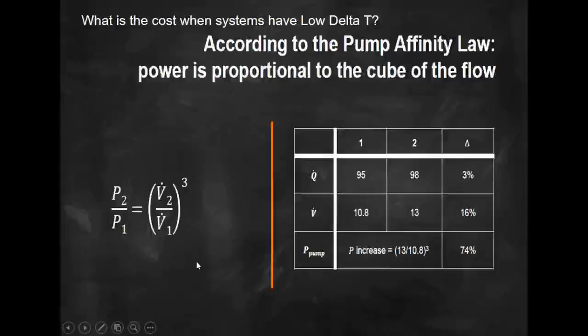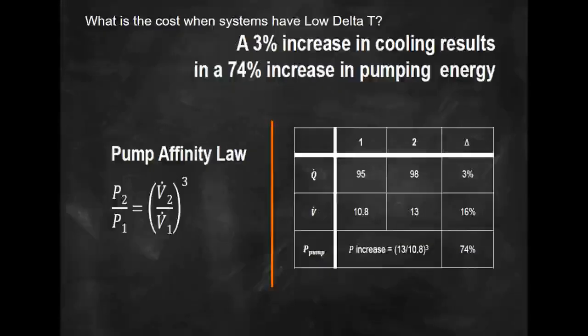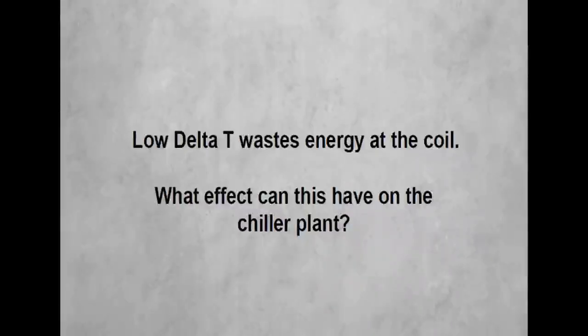But if we use the pump affinity law, which unfortunately for us is subject to the cube, then we see by calculation that we're going to consume 74% more electrical energy at the pump. So a very small nominal increase in cooling, barely visible, a sizable increase in flow, completely invisible, of course, and a massive hit on the pump because the pump's working far too hard and consuming far too much energy. Pump affinity law, we can't escape it. It's a fact. And these facts occur every day in our cooling systems throughout the Middle East. So that's the coil and the pump affected.